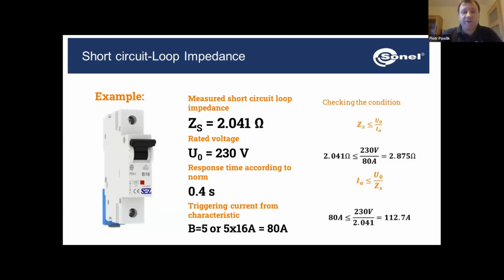And we have performed a measurement in our circuit. We got the value of fault loop impedance of 2.041 ohm. Okay, now is it good or bad? Well, here the test technician needs to evaluate the situation. However, in some of our higher model meters, like for example, Sonel MPI 540, it has a built-in database of different breakers. We can put in there B16, and after the measurement is finished, the meter will automatically evaluate the result for us. But anyway, the final decision is still based on us, the test technicians.